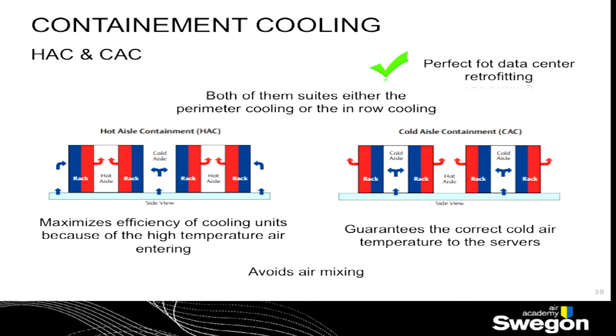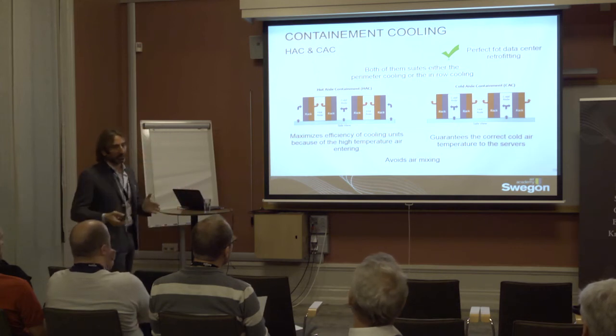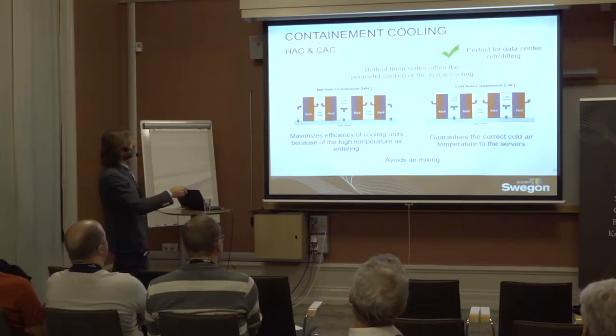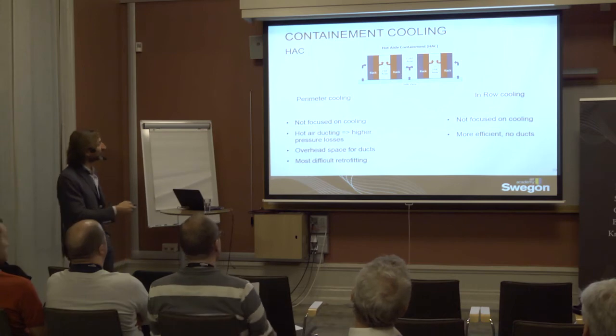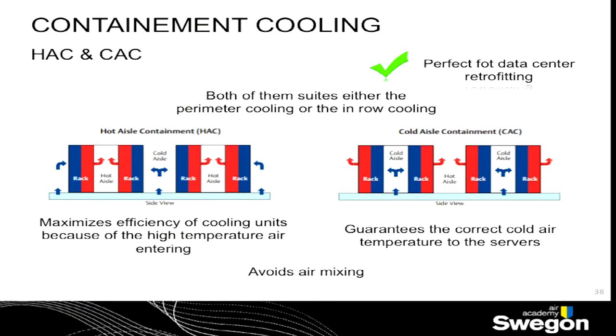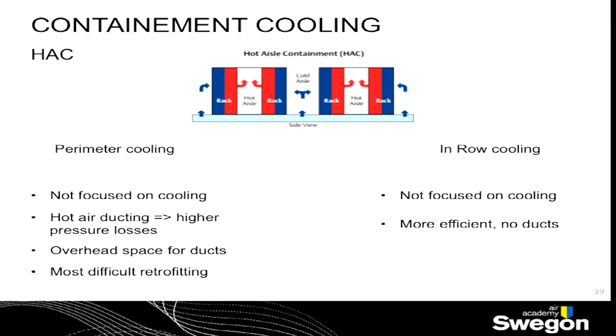We just encountered during the last presentation the difference between hot aisle and cold aisle containment. We can roughly say that this is a system that is able to maintain a stable condition for the temperature in front of the racks. So if you want to focus on the temperature in front of the racks, you have to use a cold aisle containment. Instead, if you are focused on the temperature of the return air to the system to maximize the efficiency of the cooling machine, of the chiller or of the direct expansion solution, you can use a hot aisle containment. This is the main difference. But both of them, hot aisle or cold aisle, maximize the efficiency of the system. And it is the best solution for a retrofitting, because many times the data center is just realized in a way that it is quite easy to divide the cold aisle from the hot aisle.